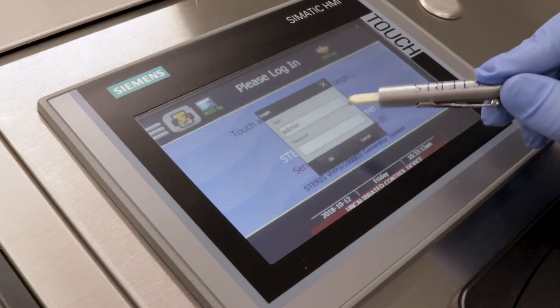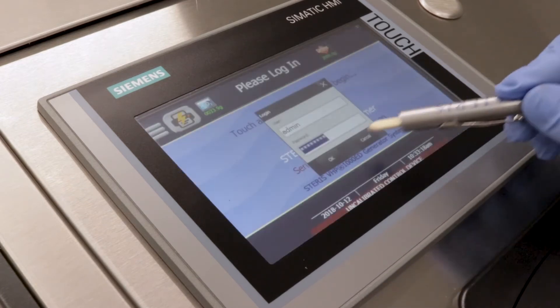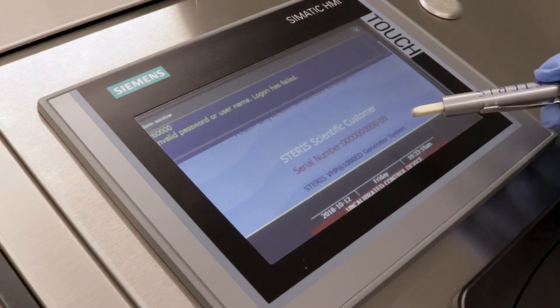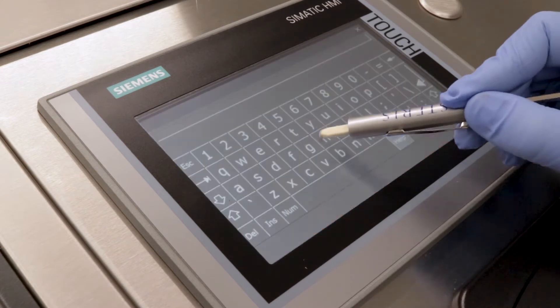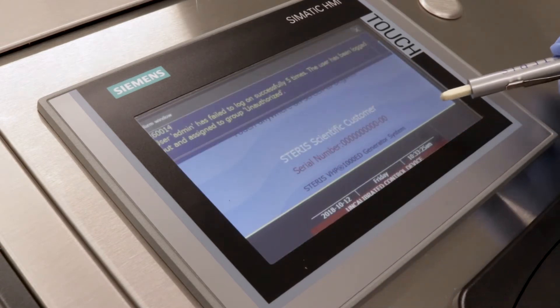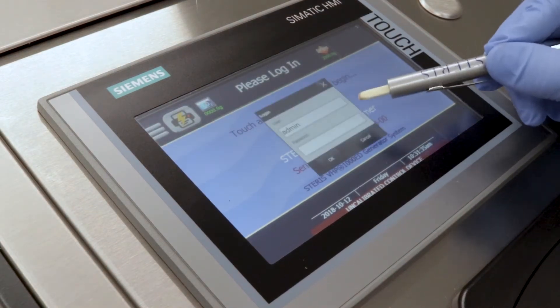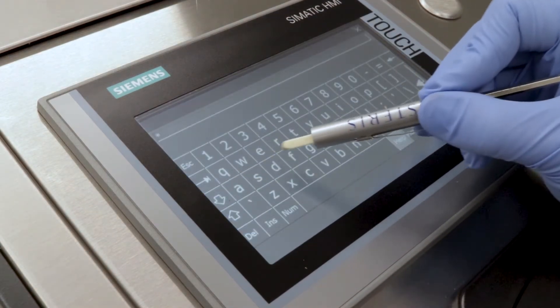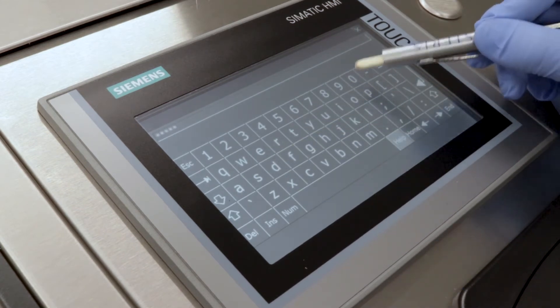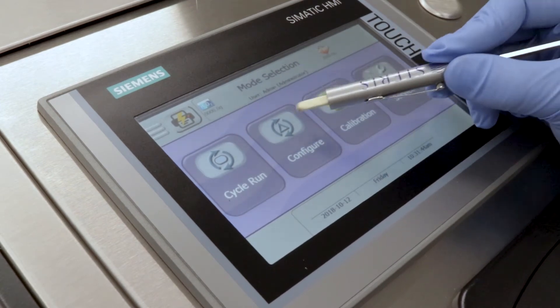One key element of STERIS's electronic data security feature is password administration and e-signature. Users log into the system by entering their username and password. The user will have five total attempts to enter valid login information before being locked out of the system. The system will require the creation of a new password every 90 days to ensure account protection. An optional user authentication feature allows users to log in with their building network username and password credentials.